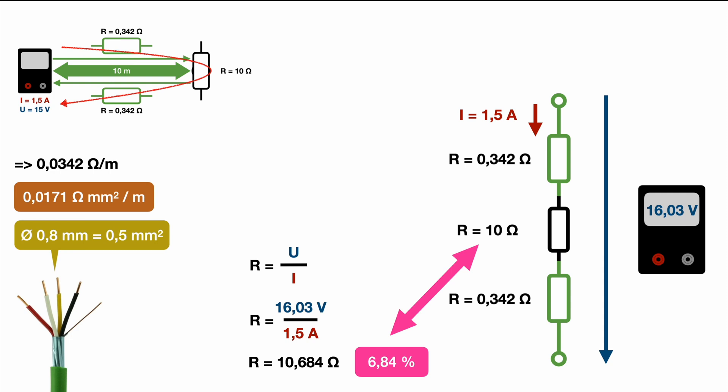But on the other hand also if the cable length would be more than 10 meters and in reality that's actually the case quite often if you're measuring like a factory or an office building the measurement wires can get quite long. So it's always about the ratio between the resistance of your cable and the resistance you try to measure and that's influencing your relative measurement mistake.